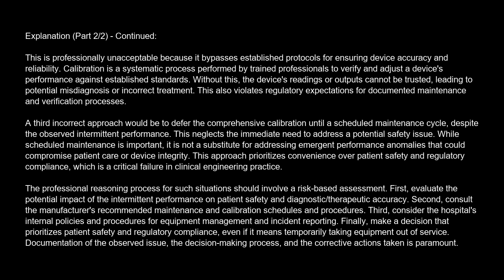Calibration is a systematic process performed by trained professionals to verify and adjust a device's performance against established standards. Without this, the device's readings or outputs cannot be trusted, leading to potential misdiagnosis or incorrect treatment. This also violates regulatory expectations for documented maintenance and verification processes. A third incorrect approach would be to defer the comprehensive calibration until a scheduled maintenance cycle, despite the observed intermittent performance. This neglects the immediate need to address a potential safety issue.